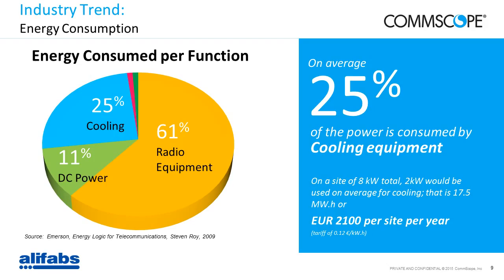Our objective is to drastically cut that quarter of your energy consumption. The great majority, hopefully. In some cases, typically it will vary between 60% and 80%. This varies because of mainly three factors. The first factor is the climate, obviously, whether or not you can use free cooling, the temperature set points at which you are happy to run your site, and the heat load from the site. So there are the three key factors. But potentially, as you can see, in absolute value, up to 2,100 euros per year per site. And that's for a 8 kilowatt site. So these are sites that we frequently see on the network.